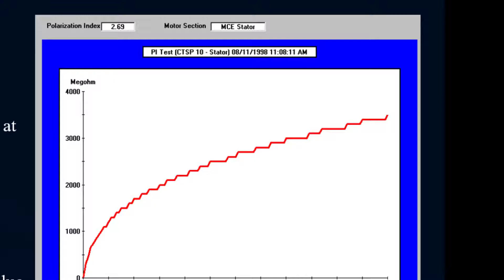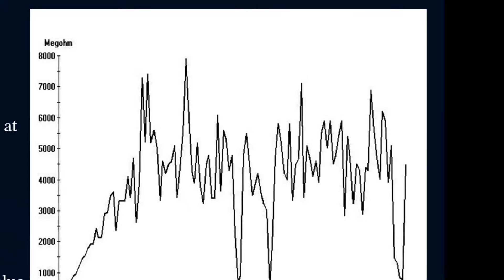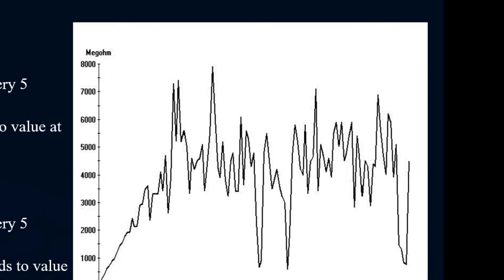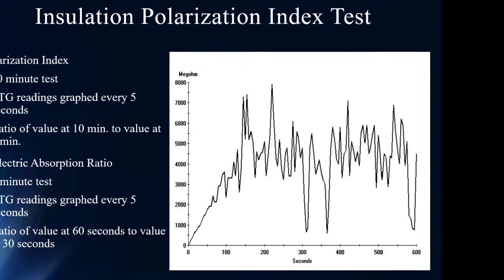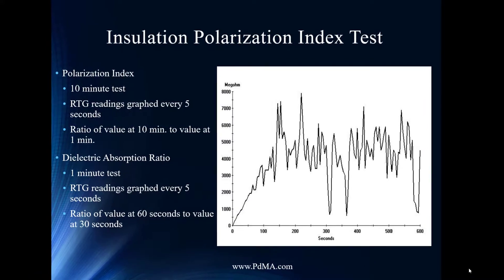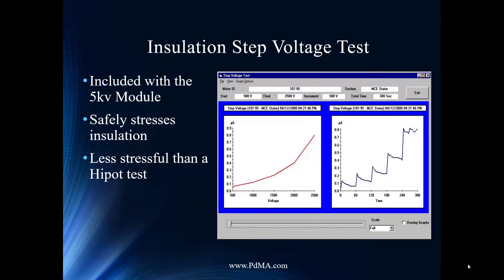The PI number is calculated by dividing the 10-minute reading by the 1-minute reading. What makes PDMA unique is that we show the full profile. For example, you might see a 10-minute value around 4,500 megaohms and a 60-second value around 1,500 — technically over 2 by IEEE standards — but the profile itself is erratic, indicating contamination, moisture, or some other issue discharging throughout the test. Even if the number falls within the recommended range, the profile would flag this for investigation.